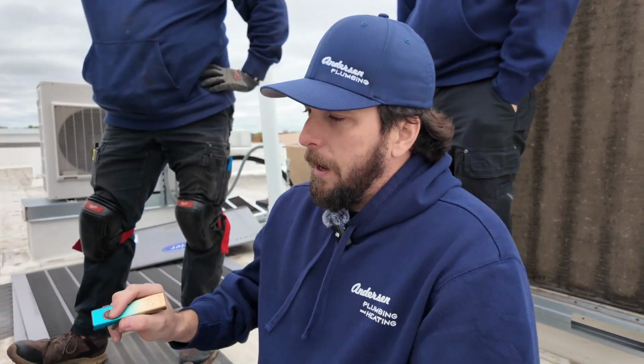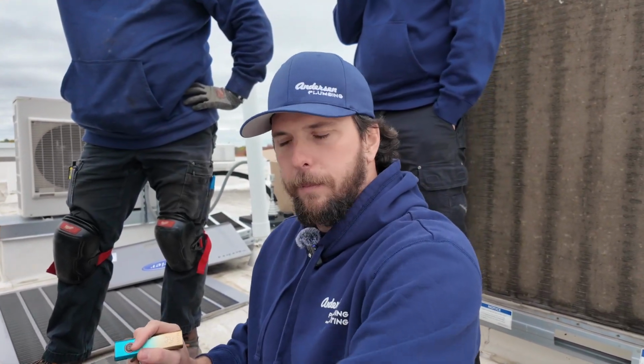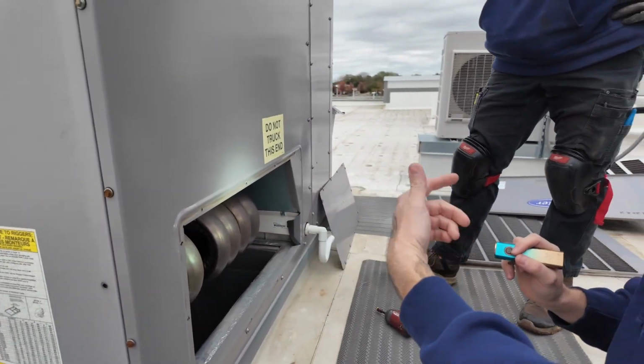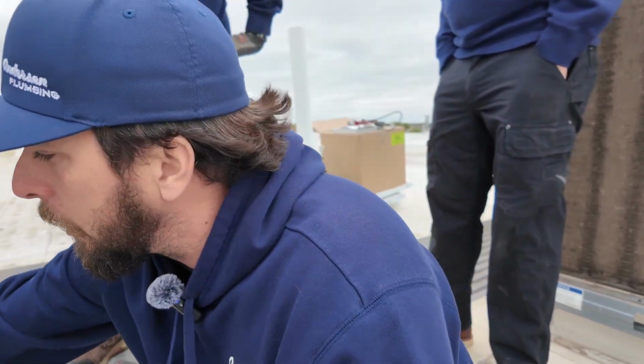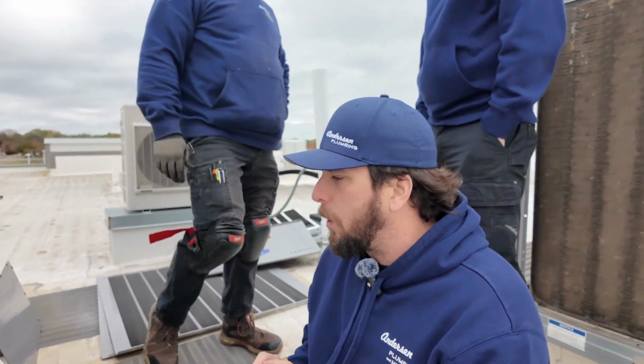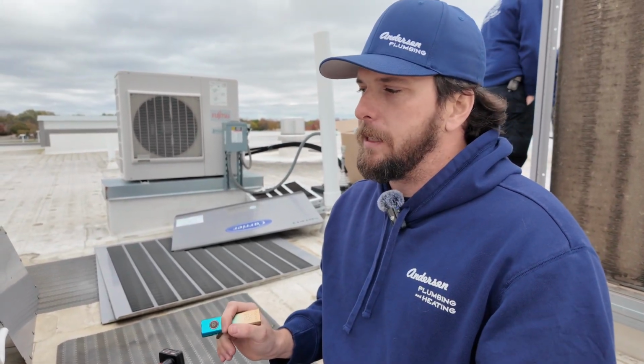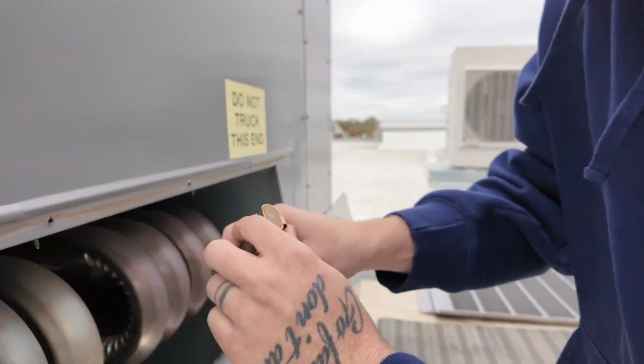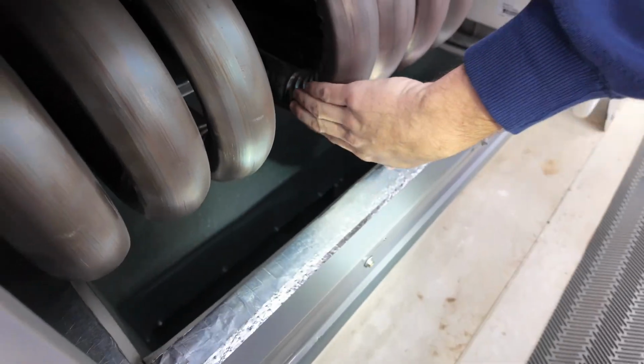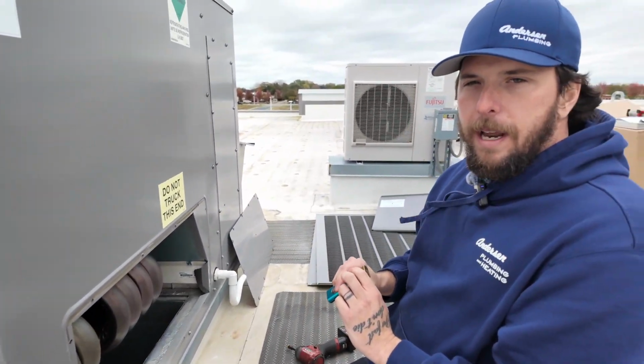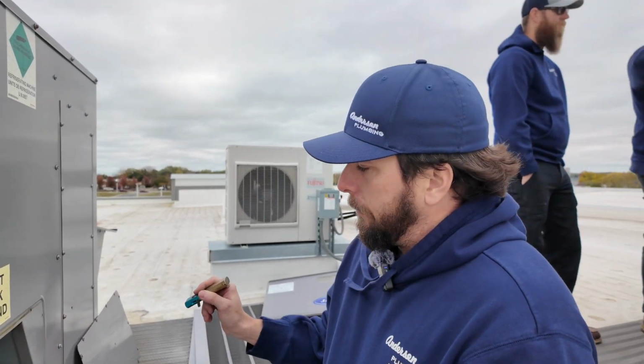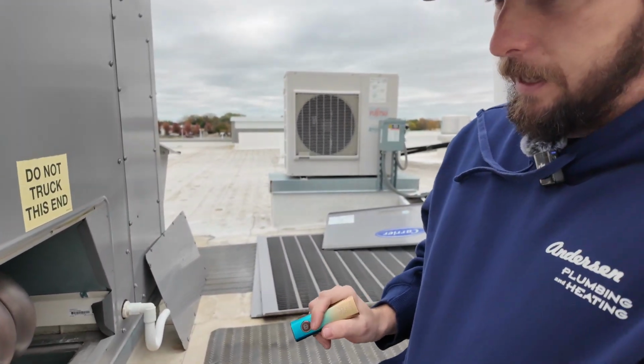The importance of a heat exchanger: those first parts we talked about, the burners. The gas and the fire basically goes into the heat exchanger, and then we blow air across the heat exchanger, and that's how we get our heat. Now, if you have any sort of a crack or a perforation or a tear or a rust hole or anything like that in the heat exchanger, the carbon monoxide from the gas being burnt is then being released into the conditioned space. If you look straight down here, this is your ductwork. This is what goes out to the whole building in order to supply the heat. So if we have carbon monoxide leaking from one of these units, it's going down into the conditioned space where everybody's hanging out. And obviously we all know that breathing carbon monoxide is less than ideal.